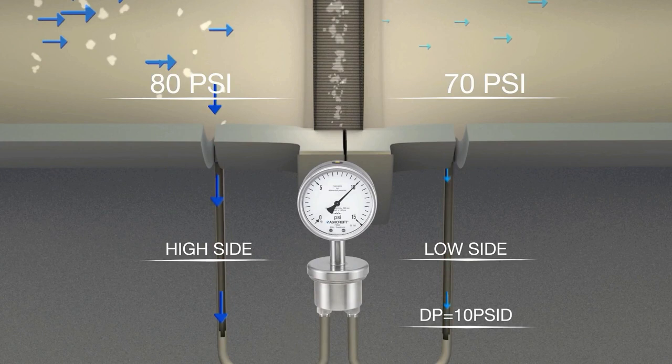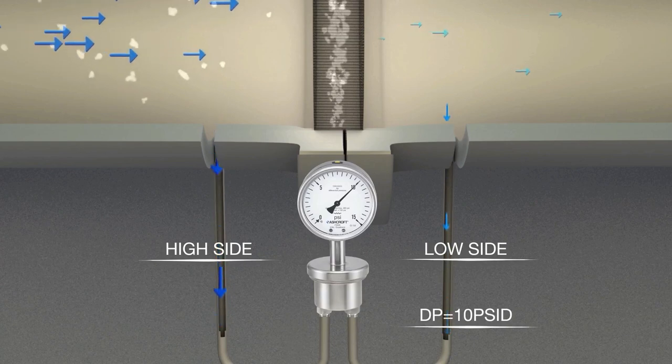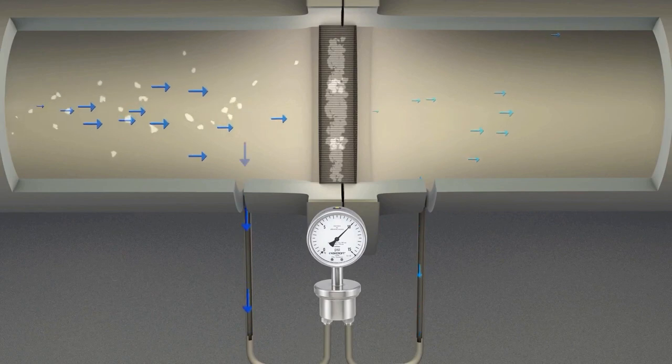When specifying a differential pressure instrument, there are two important factors to consider. The first is the DP range, which is based upon the most difference in pressure that the restriction is likely to produce. The second is the instrument's ability to contain the static pressure, which is simply the pressure in the line. While the differential pressure remains the same, a higher line pressure may require an instrument rated for higher static pressure.